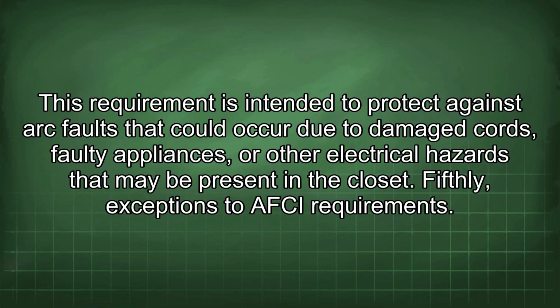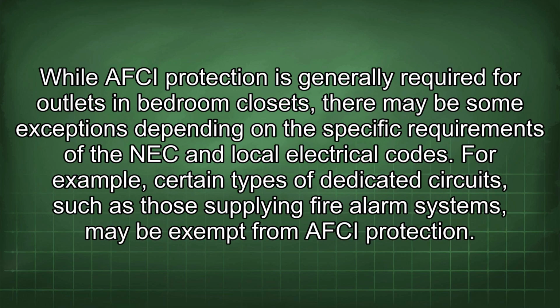Fifthly, exceptions to AFCI requirements. While AFCI protection is generally required for outlets in bedroom closets, there may be some exceptions depending on the specific requirements of the NEC and local electrical codes. For example, certain types of dedicated circuits, such as those supplying fire alarm systems, may be exempt from AFCI protection.